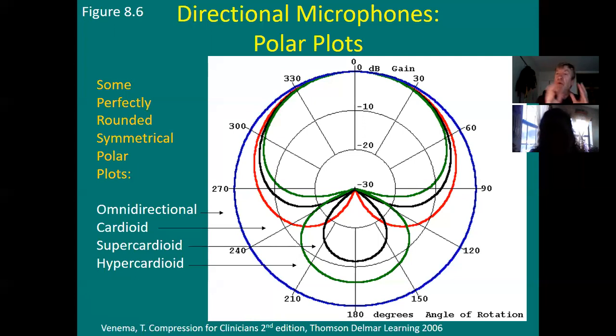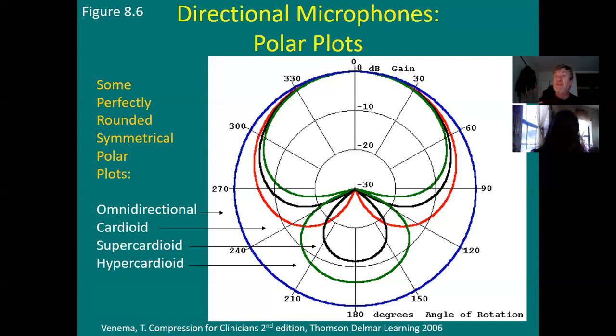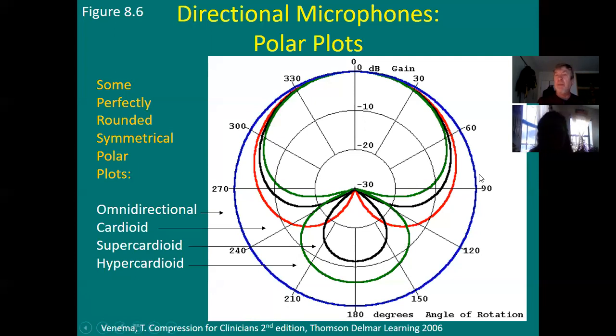These are just different polar plots. You might want one depending on your situation — like a taxi driver who wants a figure-eight pattern to hear a client sitting behind. What is digital about the mics is that digital hearing aids can change polar plots. Some do it in different programs — you can manually choose a listening-in-noise program. Some directional mics adapt and change automatically so you don't even have to make the change.